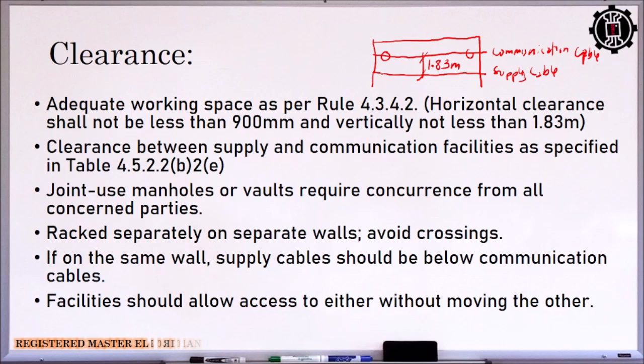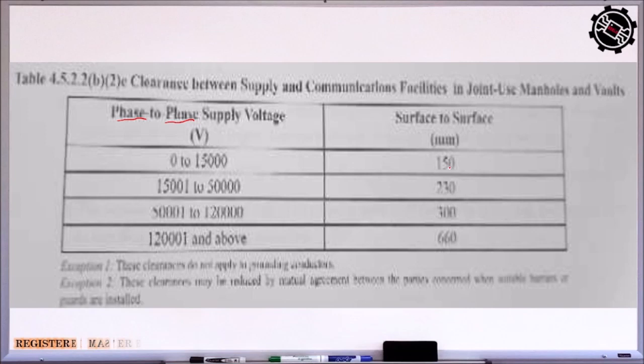Clearance between supply and communication facilities in joint use manholes and vaults. So we have the phase-to-phase voltage, which is our line-to-line voltage. For 0 to 15,000 volts, the surface-to-surface clearance is 150 mm. For 15,001 to 50,000 volts, that is 230 mm. For 50,000 to 120,000 volts, that is 300 mm. Then 120,000 volts and above must be 660 mm.